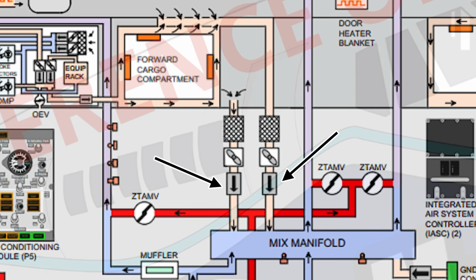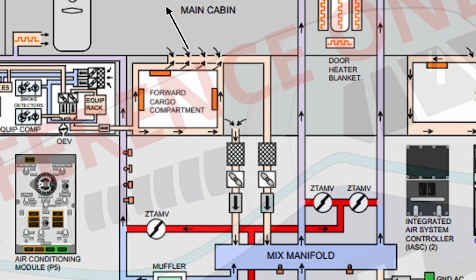The arrows that you see are the recirculation fan check valves. They are there to stop conditioned air from the mix manifold from flowing back through the recirculation fans into a cabin zone if the recirculation fan is off.